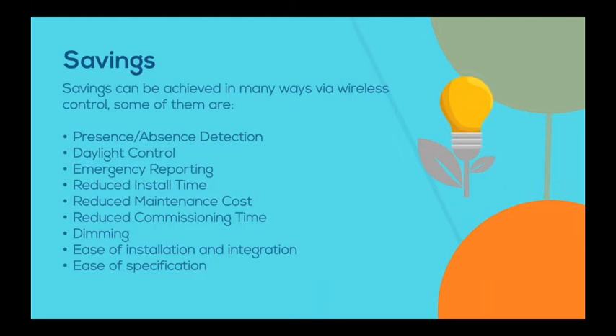From a maintenance point of view, with a traditional DALI system, having to pay every time a driver drops out - £500-600 a day commissioning time - it becomes really expensive, and in my experience was a big off-putting side of those systems to people. In terms of commissioning time, 200-300 lights a day, no problem, so when the project is finished, getting everything set up and off site is incredibly quick.